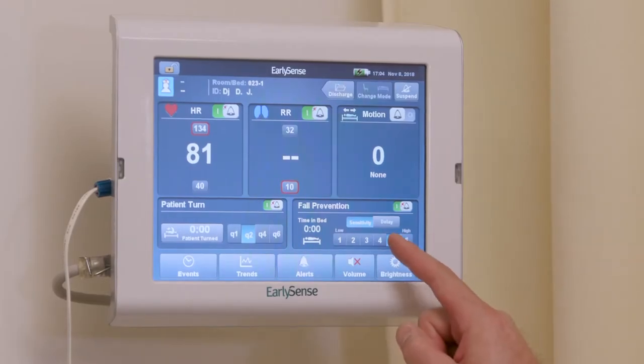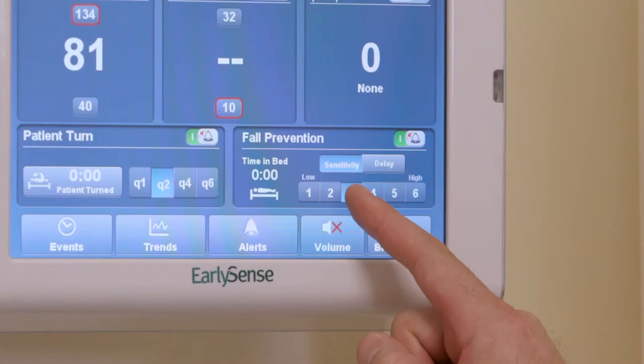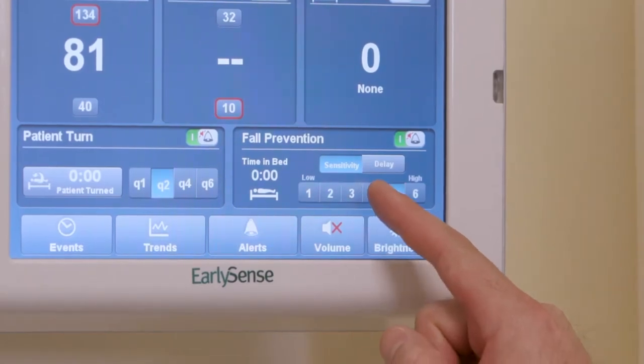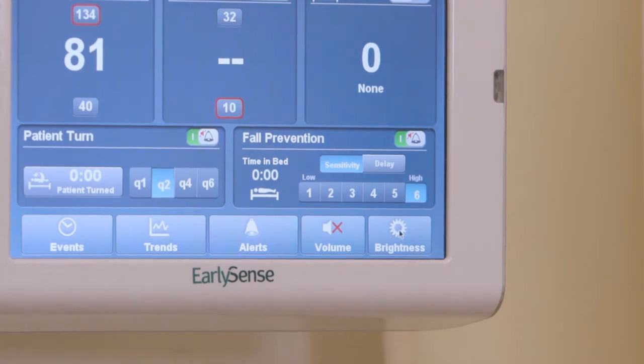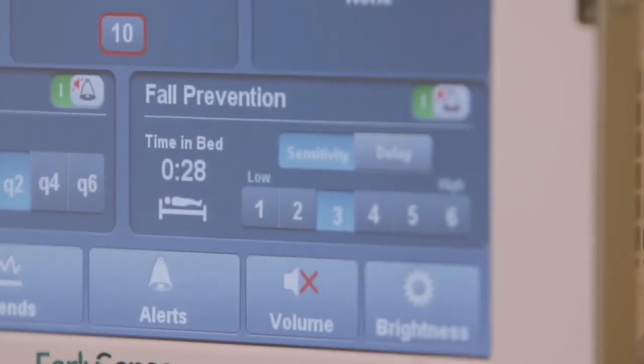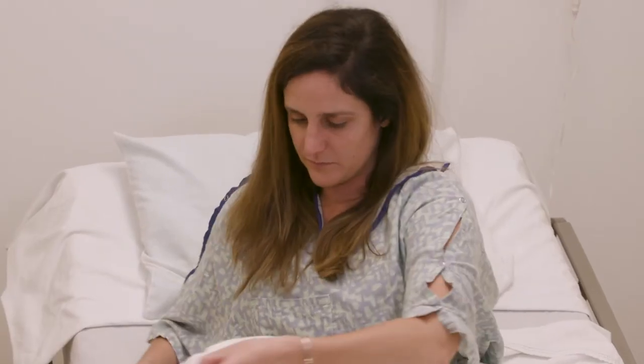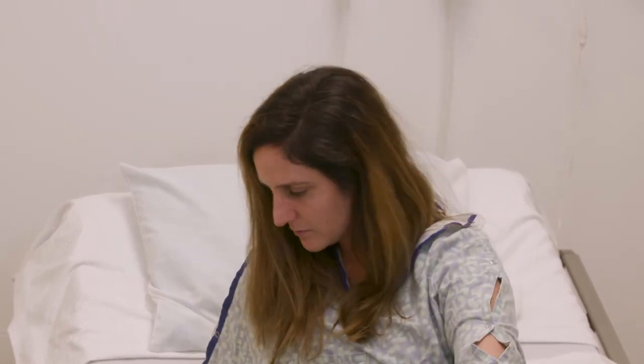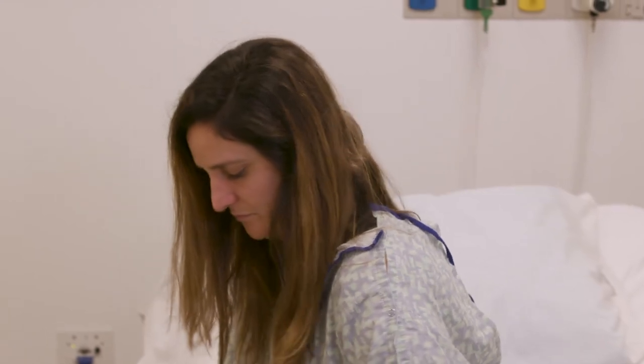Six being the most sensitive and one being the least sensitive. This means that higher fall risk patients should be on a higher number sensitivity. Sensitivities three through five are referred to as posturing sensitivities, meaning the system would alert for a bed exit if the patient's back came forward off the sensor, or if they were sitting on the edge of the bed or chair.